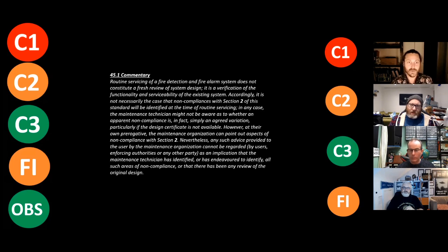Yeah. Like you need to, and this is the point of the initial takeover visit. It's really important because the standard is written in a way that, Will might comment on this, under the assumption that any system installed is to the standards, but we know they are not. And to be fair, 7671 does as well. Inspection and testing is based on the assumption that the system installed met the standard, but we know it doesn't. That's why you have to use your engineering judgment here, because what a lot of companies do, they take over systems and they're just testing detectors and call points and say, yes, they work. But it doesn't mean it's a fit for purpose system.